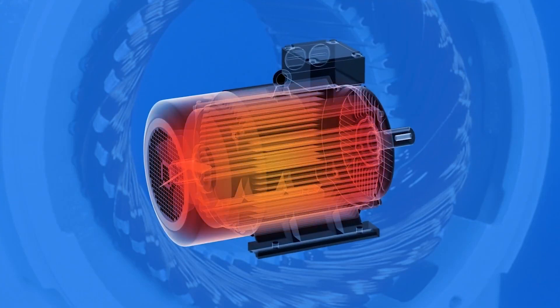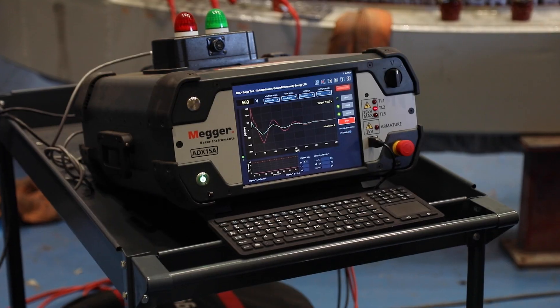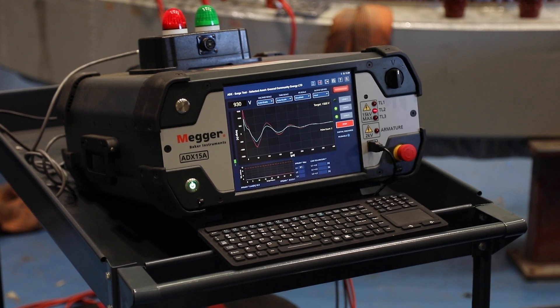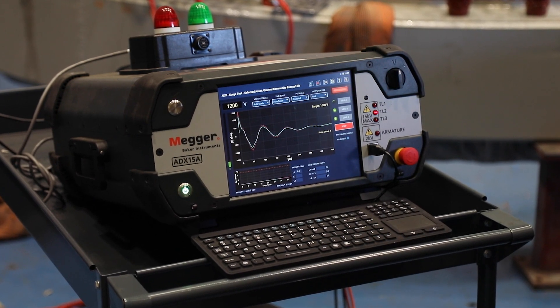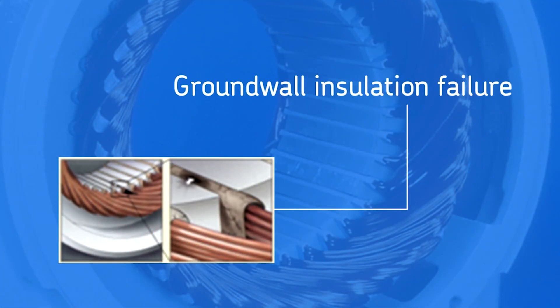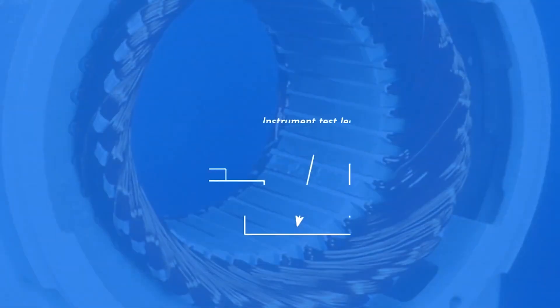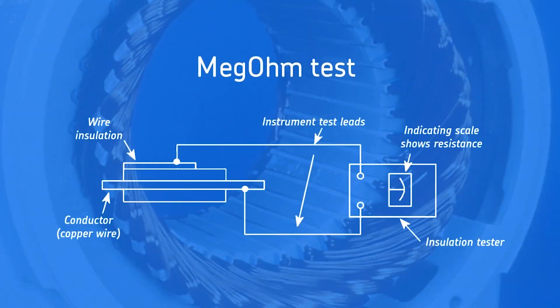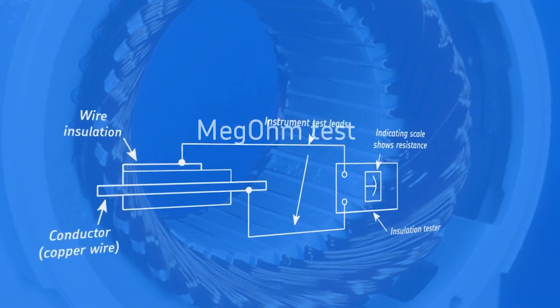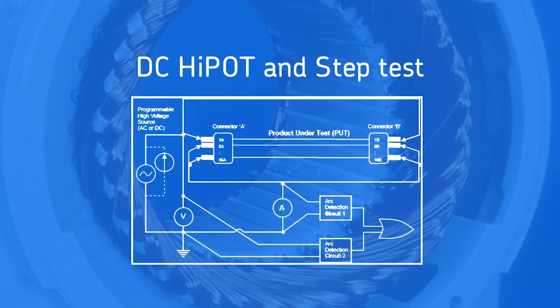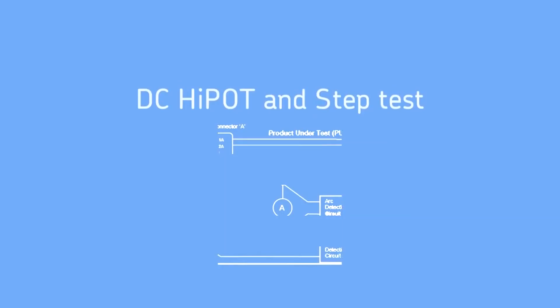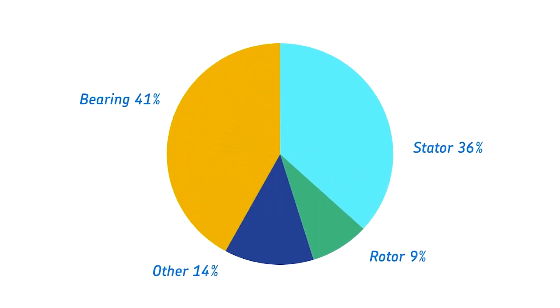When a turn-to-turn fault occurs, the motor will draw a lot of current, quickly overheat, and can melt down in minutes. The surge test can reliably find the strength of turn-to-turn insulation, giving early warning when insulation is weak. When insulation fails and there is a path to the core, it is called a ground wall insulation failure, since the stator core is at electrical ground. Ground wall insulation strength is measured with the megohm test at low voltage, but this test misses many failures. A better test is the DC high pot and step test, which measures insulation strength at higher voltages. Stator insulation faults are responsible for about 30–40% of motor failures.